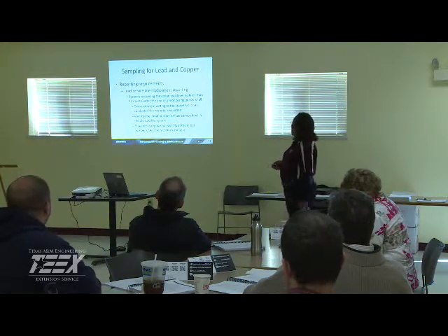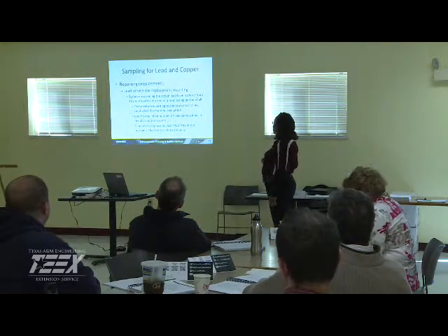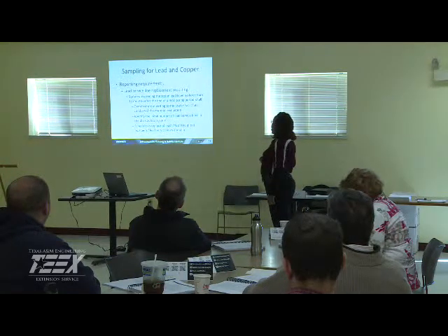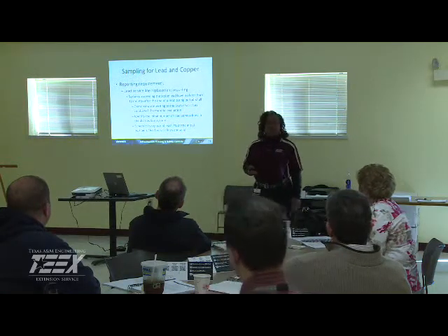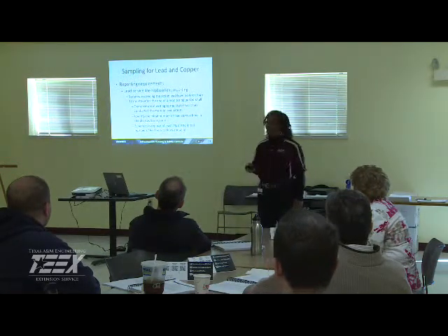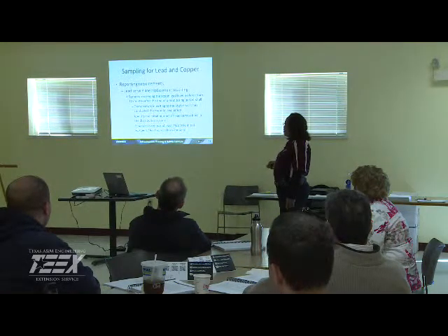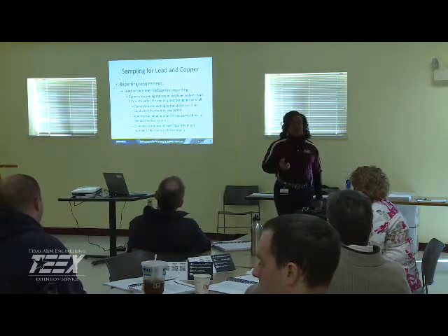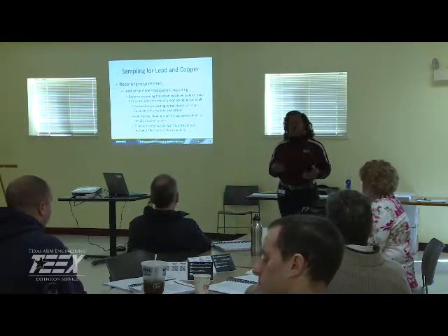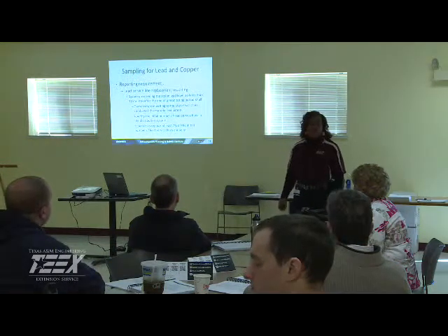All right, continuation. Lead service line replacement reporting. Now, what happens if you had hot spots? One of the things was that the EPA says that you need to start scheduling replacing some of the lines, and the stipulation was to shoot for at least 7% on an annual basis as far as replacement.